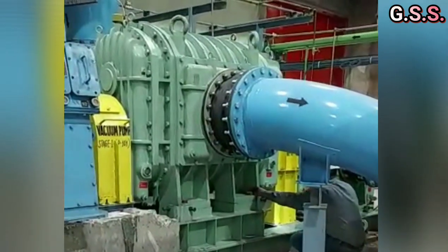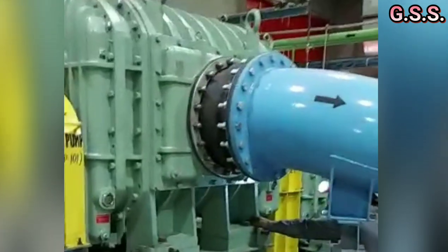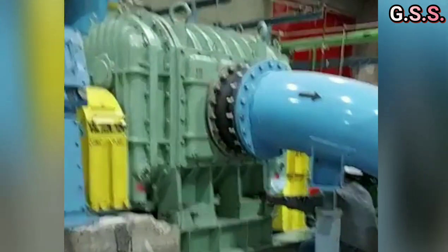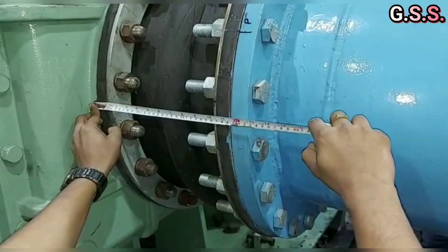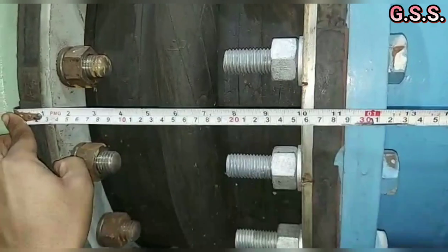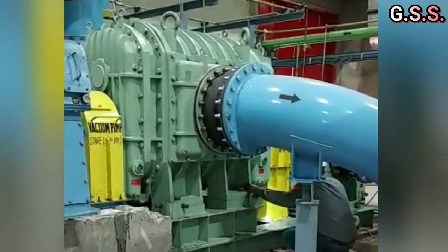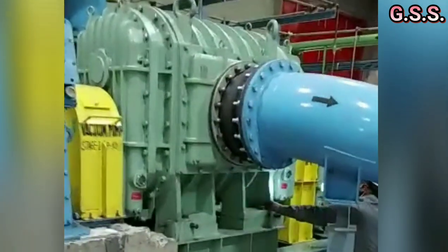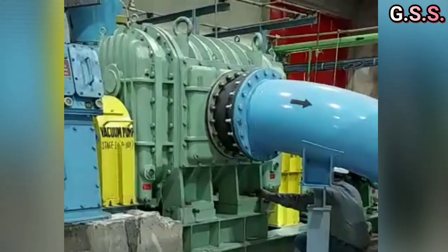But in this air blower installation, bellow tie rods have not been installed and when air blower discharges air at 1 bar gauge pressure, the bellow expands axially by about 1 inch. And this bellow installation is unsafe because axial pressure thrust is transmitted to the piping system and to the blower nozzle also.